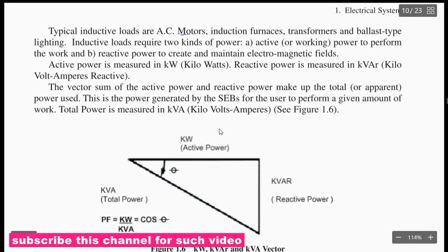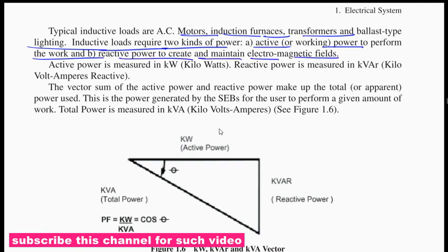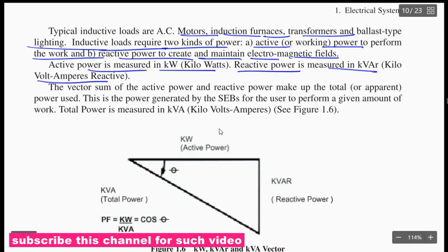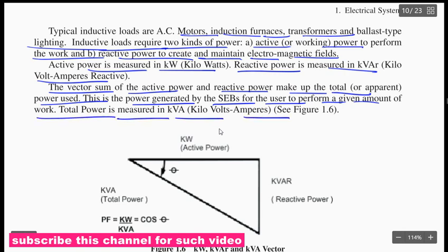Typical inductive loads are AC motors, induction furnaces, transformers, and ballast type lighting. Inductive loads require two kinds of power: active power, that is working power to perform the work, and reactive power to create and maintain the electromagnetic field. Active power is measured in kilowatt, reactive power is measured in kVAr, kilovolt ampere reactive. The vector sum of active power and reactive power makes up the total apparent power. This is the power generated by the utility to the user to perform the given amount of work. Total power is measured in kVA, kilovolt ampere.